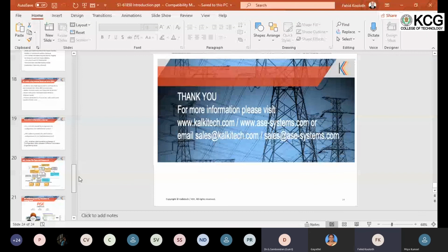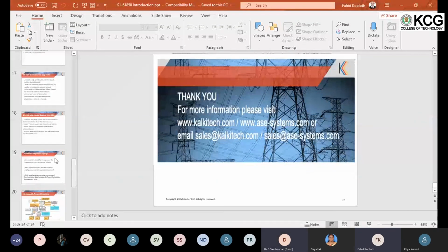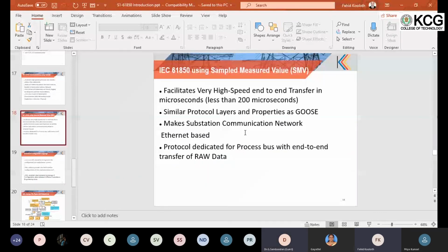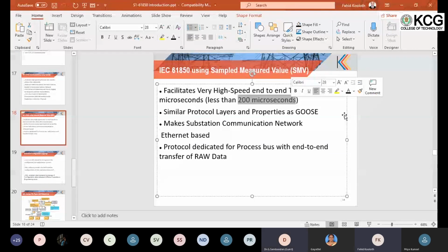Actually, as I mentioned, sample value is transmitted over the Ethernet directly. That is, the Ethernet layer is used for the sample value transmission. So other overhead like TCP, IP is removed, and it goes directly onto the Ethernet level, and the standard facilitates you to transmit up to 200 microsecond level on the process bus using sample value. And dedicated fiber optic fast Ethernet is specified to ensure that this data gets transmitted faster.